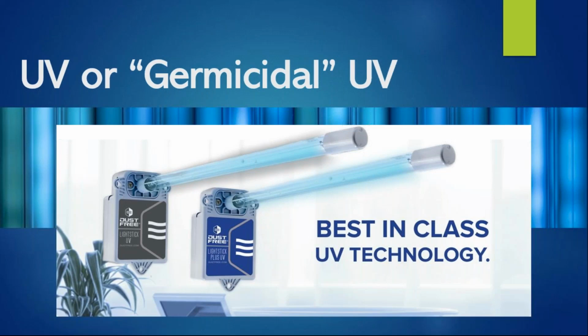Along the way, a few years ago too, there were several companies out there, and I was guilty of it too. We used to put these lights in the return air drop of split air systems, and we were thinking that it was a form of an air purifier. UV needs 2 things for it to be effective. You need exposure time to the lamp, and you need to be pretty much right on top of the lamp in order for a microbe or a germ to get zapped or killed. So those 2 things are required.